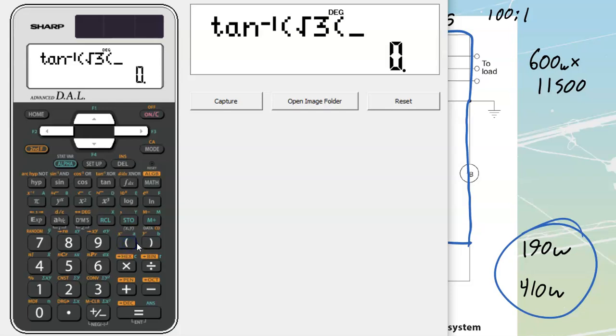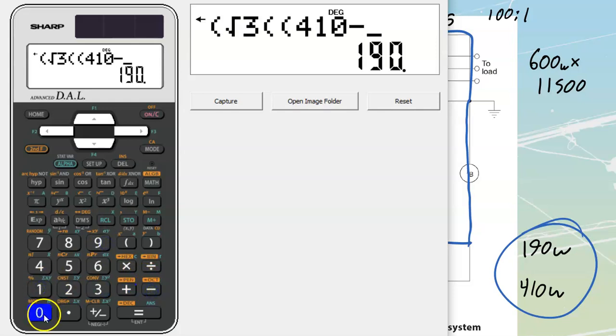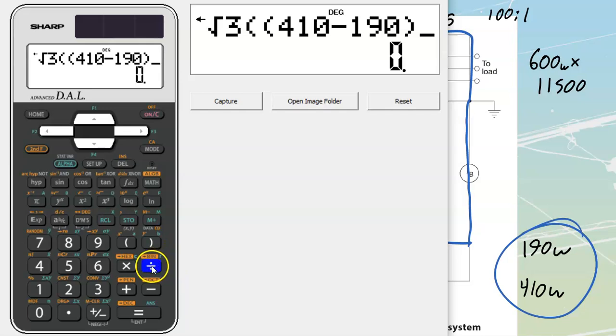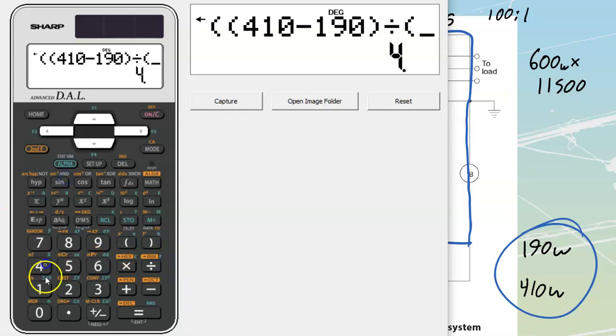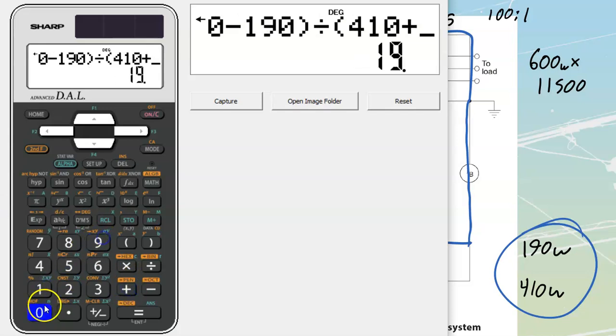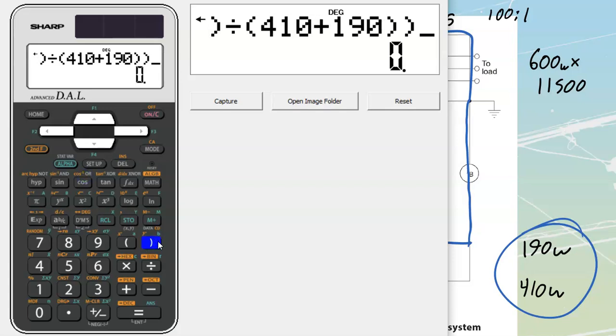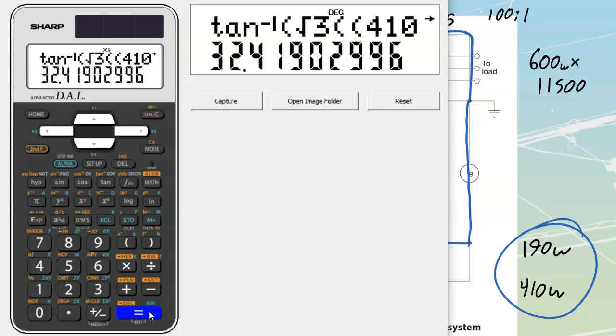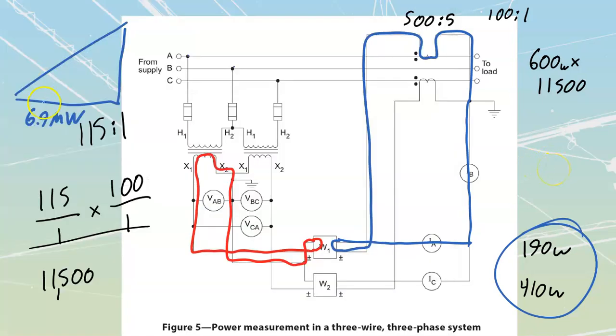bracket. So that's going to automatically multiply by wattmeter 1 minus wattmeter 2. So that is going to be my larger minus my smaller: 410 minus 190, divided by 410 plus 190, bracket, bracket, bracket. 3 brackets to close this whole thing off. And when we punch that through, we end up with a value of 32.4 degrees. So I know what my phase angle is, 32.4 degrees over here.